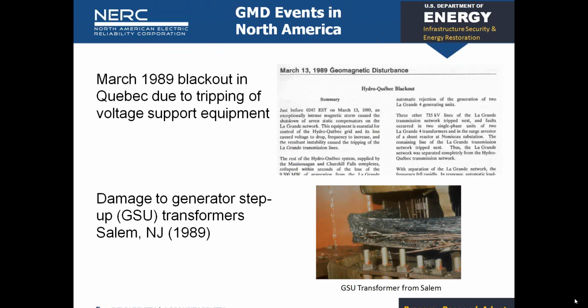Secondly, equipment damage was also noted during that storm, and this occurred here in the United States. Some generator step-up units in Salem, New Jersey, during the event, experienced an increased reactive power demand, and measured dissolved gas increases were observed, which is an indication of the hotspot heating that might have been occurring inside the transformers there. After the event, the units were taken offline and examined, and they had damage inside that resulted in them having to be replaced. There were design factors involved, but it was an example of where geomagnetically induced currents caused a problem with transformers.